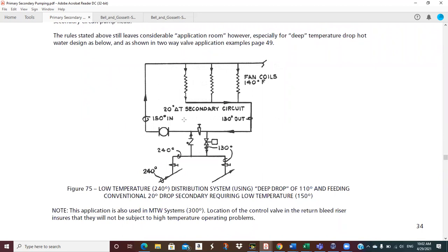The rule stated above still leaves considerable application room, especially for deep temperature drop hot water design, as shown in the two-way valve application examples on page 49. So you go back and look at those, but this is one of them. And so you see here, this is where this is probably going to work. I've got 240-degree water, and I'm going to mix it to the point that I have 150 over here, and I've got a 20-degree drop in my secondary, and I've got a 110-degree drop for my primary water, because I'm 240 here, and I'm going to return at 130. So that's pretty good.